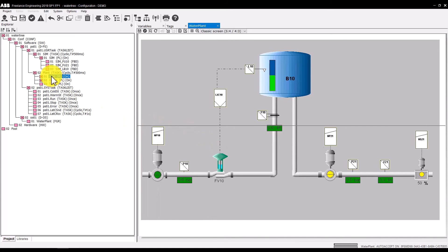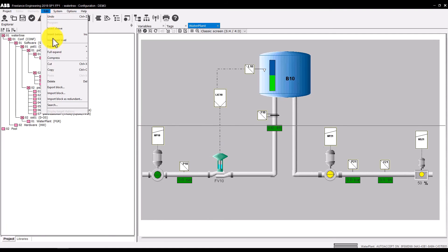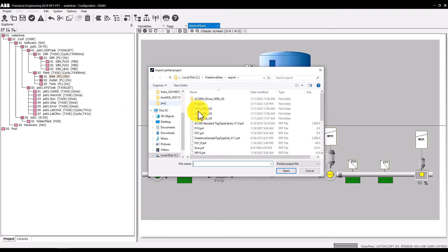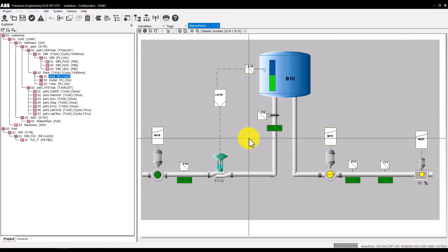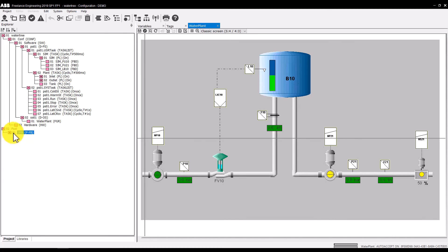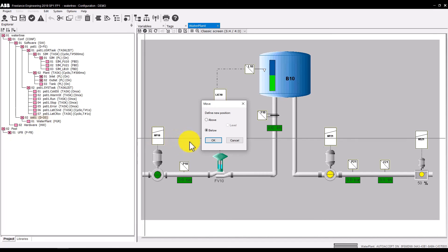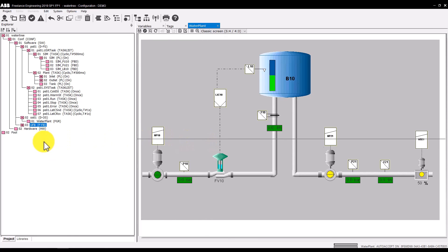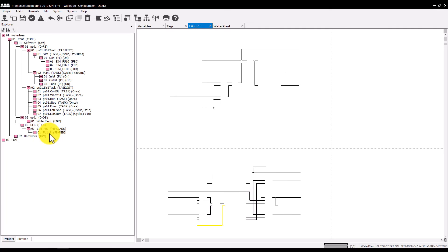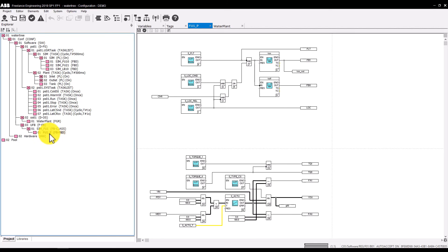What is missing is the user-defined function block. To import it, select the Edit Import Block command. Select the corresponding file and prevent automatic renaming of tag names. You see the user-defined function block was imported into the pool. Collapse it and drag it under the OS1 node. If you expand it, you see all components: the function block class and the function block diagram itself.